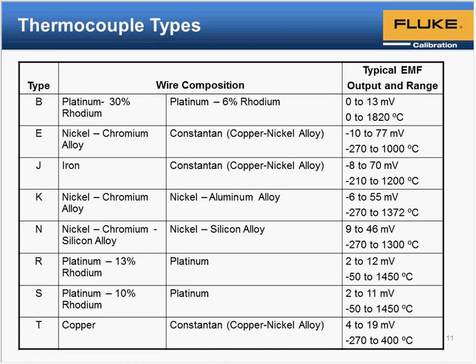The reason why type K is so popular is look at the amount of signal that it's able to produce over its temperature range. It will go all the way up to 55 millivolts. So you still have to have a really good voltmeter to measure these small changes in voltage, but you compare that with the type S and type R, where at the temperature you are only getting about 11 millivolts, and that change from only 2 millivolts at the lower temperatures. I think maybe it's to say -2 millivolts to 11 millivolts, but anyway, you have to have a really good voltmeter for these temperature or voltage changes on a type S or type R thermocouple.